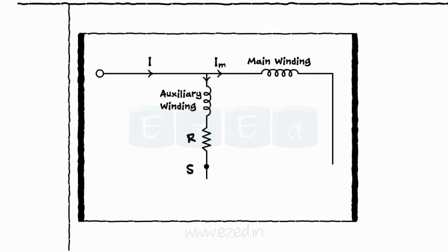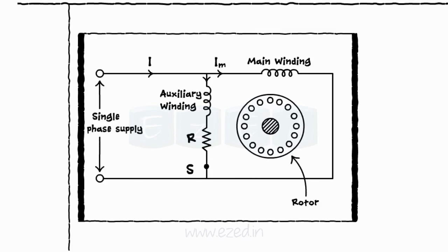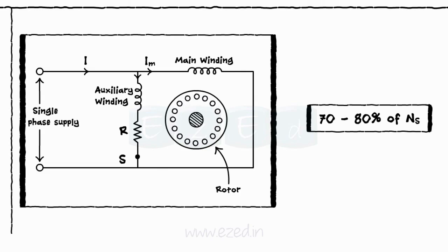A centrifugal switch is connected in series with the auxiliary winding and is located inside the motor. Once the motor reaches the speed of 70-80% of synchronous speed, the starting auxiliary winding is disconnected from the supply with the help of this switch.